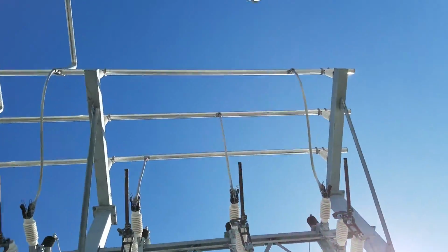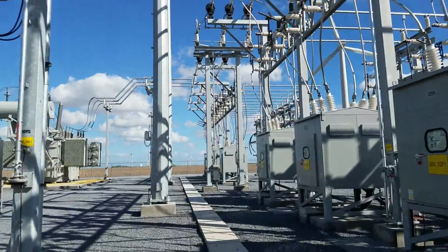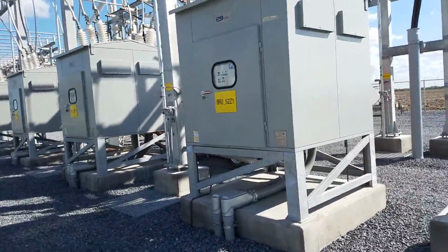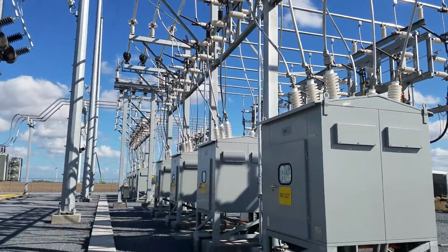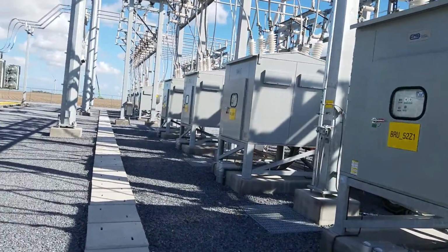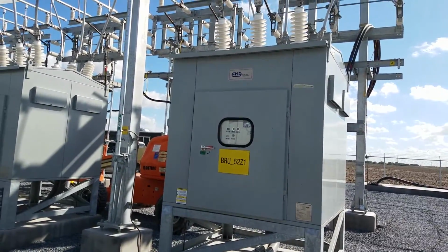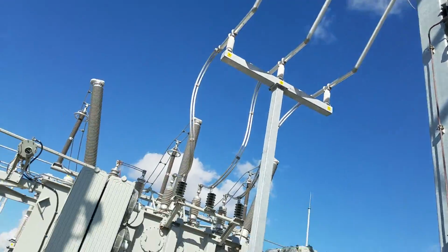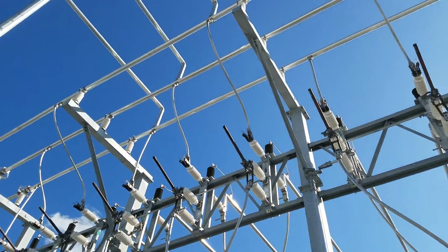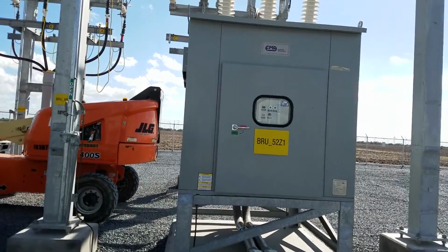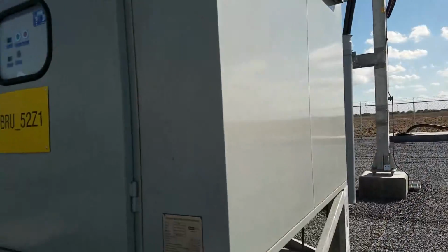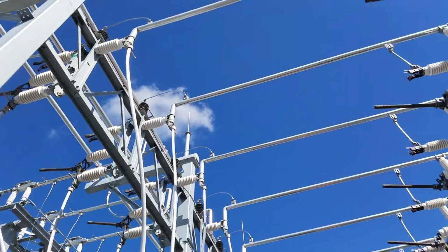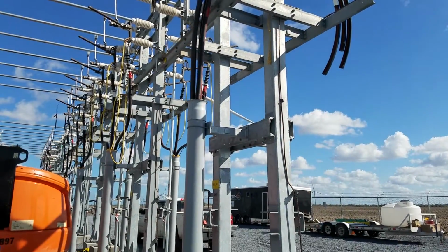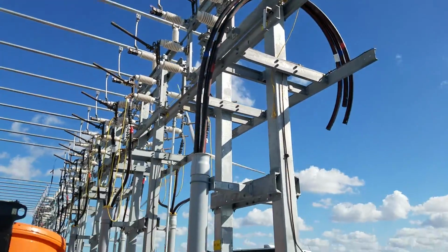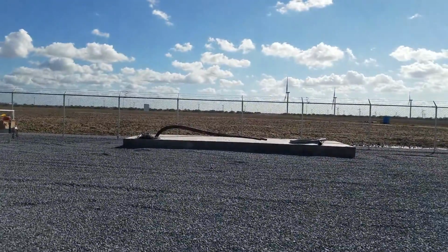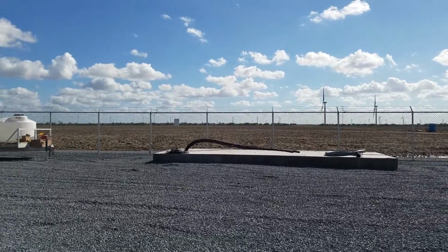Then it splits off into this bay, call it a low side bay, and it's called the low side bay because it's on the lower side of the voltage of the substation. And this substation consists of 4 breakers, 4 low side breakers. These are just like the breakers in your house, just a little bit bigger. So power comes from the transformer through the switch, then it'll go through this other switch, through the breaker, then out the other side of the breaker when the breaker's closed. And that feeds this particular bay, and this bay is for the capacitor banks. So it feeds these underground cables, and it goes over to this slab here, and the slab is where the capacitor bank will be. I think it's a dynamic capacitor bank, it's fully enclosed.